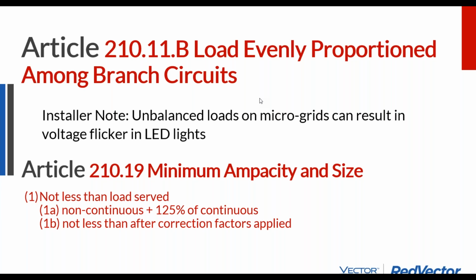power quality issues. And so if you have flickering LED light bulbs, this happens with high-end solar components and batteries as well as low end. You may want to check to see if you have the same amount of load occurring on both phases. Relocating a breaker from one side to the other can reduce that issue.